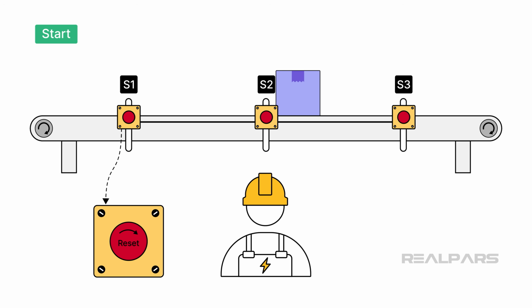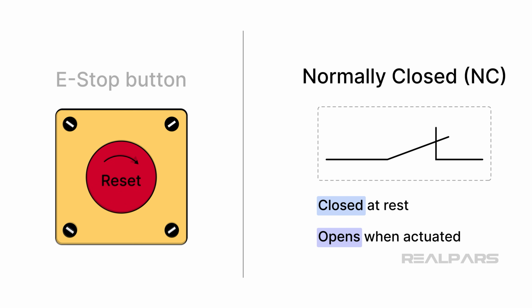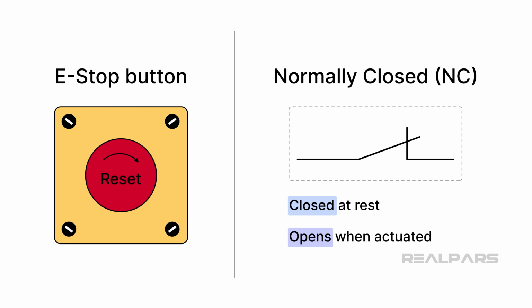An emergency stop switch is a manually operated switch that instantly stops a machine and places the process in a safe state when a perceived hazard is present. Even if the hazard is removed, the process won't restart until the e-stop is manually reset. For safety reasons, an e-stop switch is normally closed, or NC.